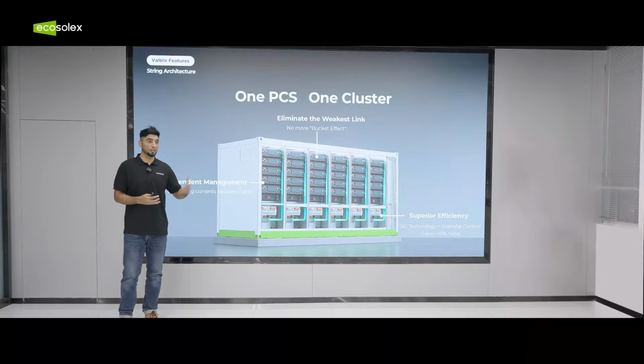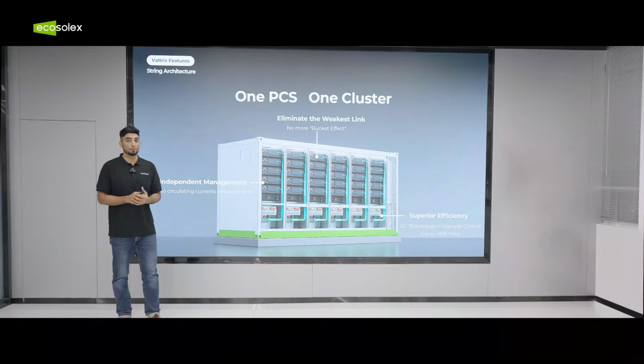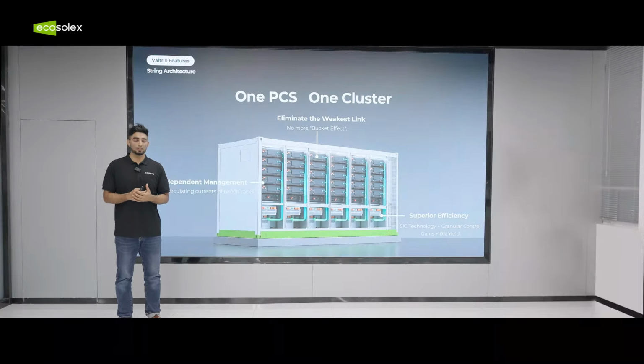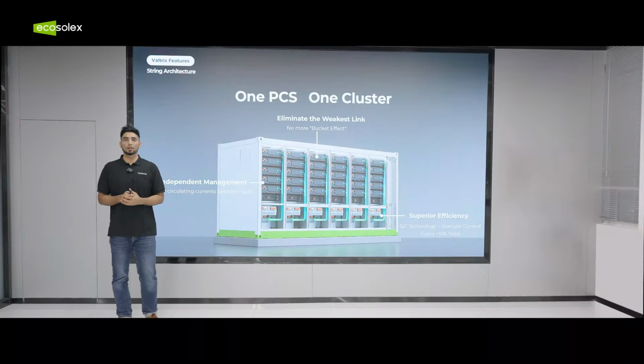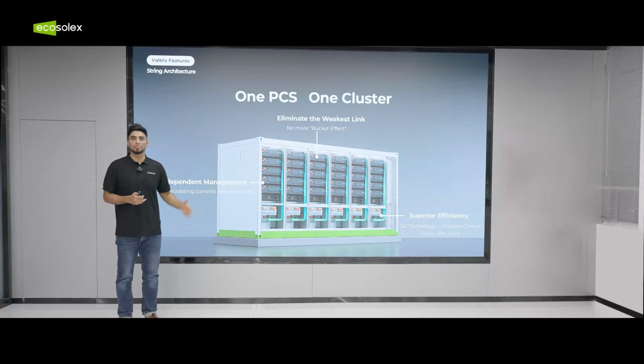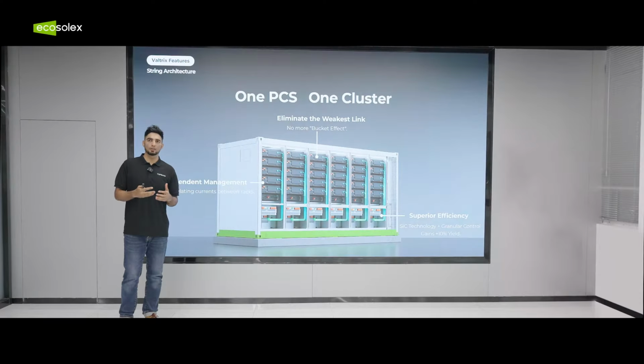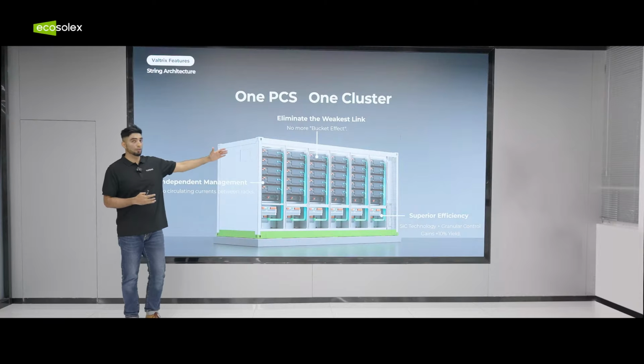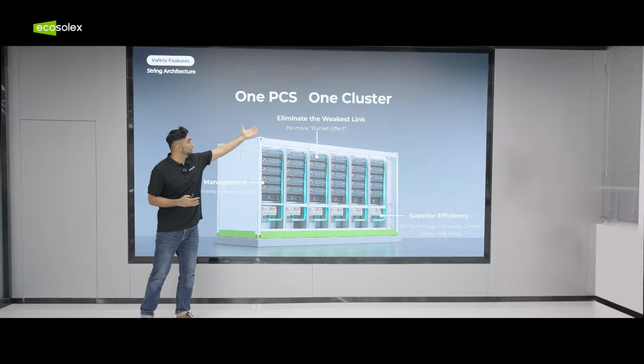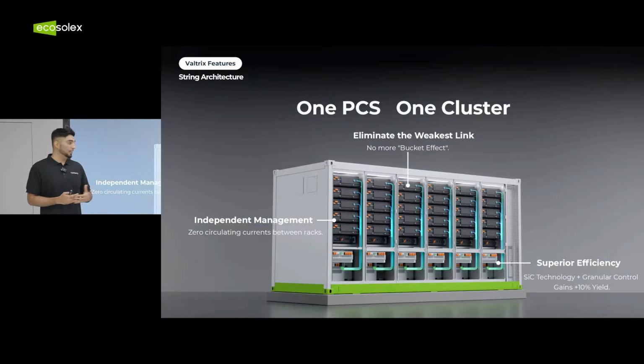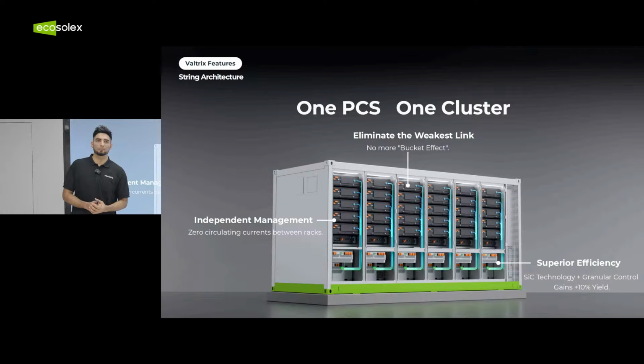Let's focus on the yield. In traditional systems, the bucket effect is a major challenge, where one weak battery can limit the performance of the whole cluster. Valtrix String 3.0 eliminates this bottleneck with a one PCS, one cluster architecture. By achieving independent management, zero circulating current between the racks, combined with silicon carbide technology and granular control, this architecture increases the system discharge yield by 10% throughout its lifetime.